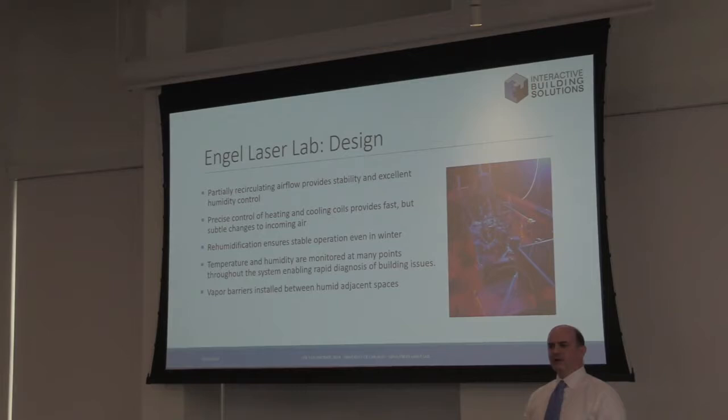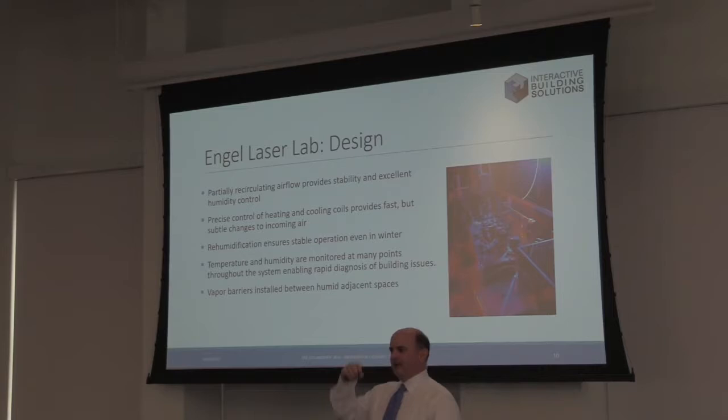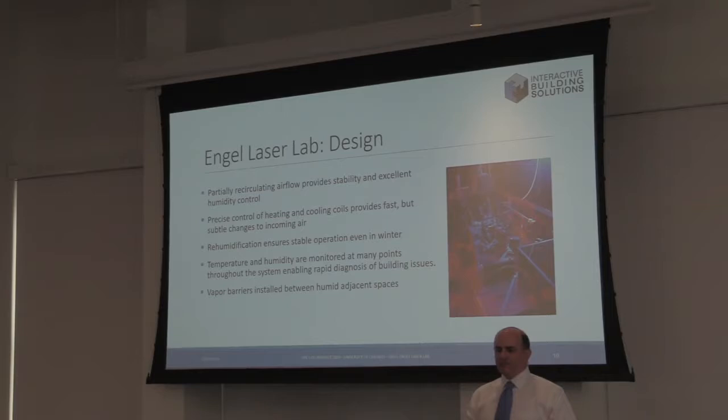Understanding how to monitor these things is also important. Making sure that you're watching the lab in the right place, which is typically right above the laser table. That's important. Making sure the bottom skin of the laser table is the same as the top skin of the laser table so the whole thing doesn't bend. I mean, sure, it's 3 tons of steel and it's 18 inches thick, but it doesn't take much for this thing to warp or stress or show torsional strain, and that'll also ruin your experiment. So there are a lot of these types of things where they really help.